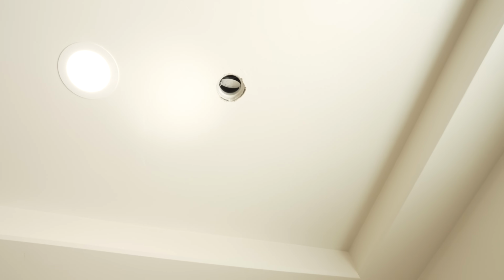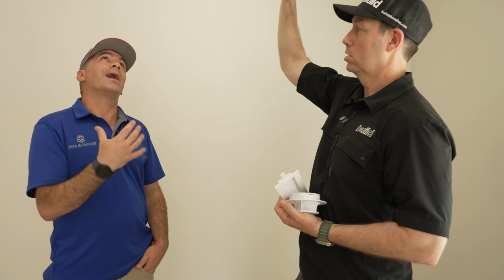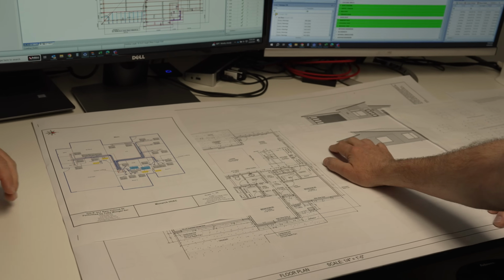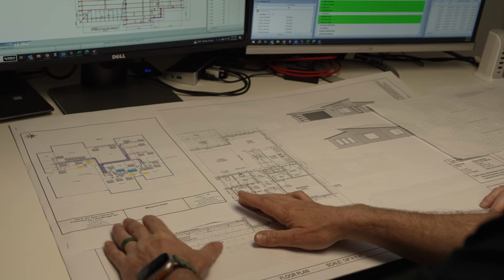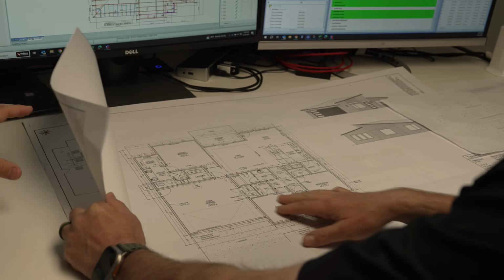Yes. So that's a 5-position damper. It can go from 0, which is all the way open, to 5, all the way closed. Okay. So during our design, we know how many CFM is supposed to come out of this. Yeah, we saw that in Matt's office. Yeah. Your design had like 45 CFM in this room or whatever.